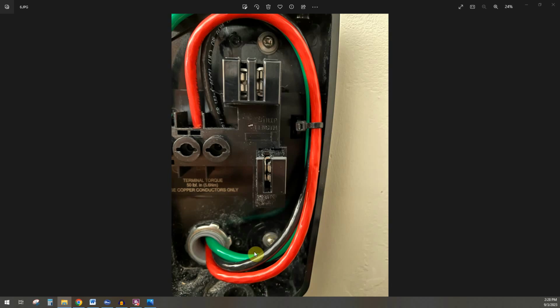These wires are thick enough that you can push them and bend them how you want and they'll stay like that, because it's a decently thick wire. So just make sure you push it as far away as you can from these sliding contact edges, because when you heat up wires, they do move a little bit because of all that power going through them. If it's too close, there's a chance the insulation starts rubbing on these edges, and you know where that goes. Rubbing insulation, bare copper showing, you start a fire. So make sure you keep those as far away as possible so they don't touch.